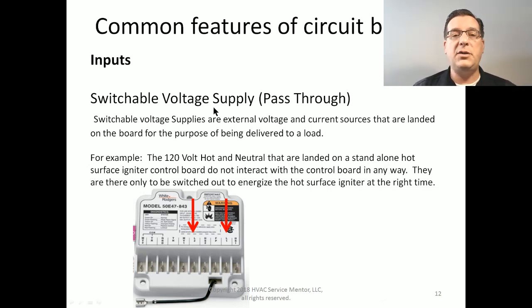Another input, like we talked about, is the switchable voltage supply, also known as a pass-through. Switchable voltage supplies are external voltage and current sources that are landed on the board for the purpose of being delivered to a load. For example, this is a hot surface ignition controller. It's powered by 24 volts, but it has 120 volt hot and 120 volt neutral landed on it. These are there because the job of this controller is to send 120 volts to the igniter. The igniter runs on 120 volts. So that's why it needs to have 120 volts coming into it, so that it can send 120 volts out to the igniter at the right time.